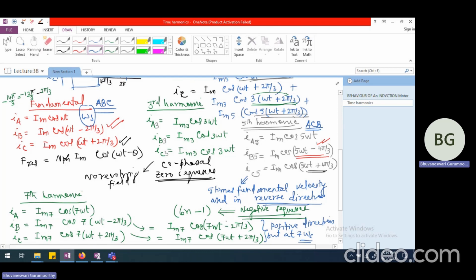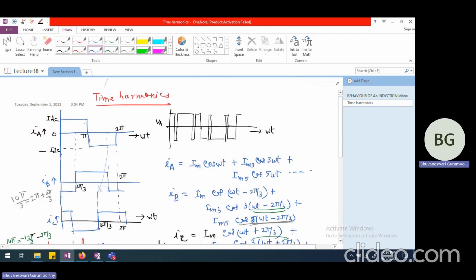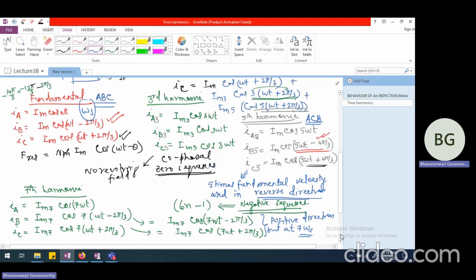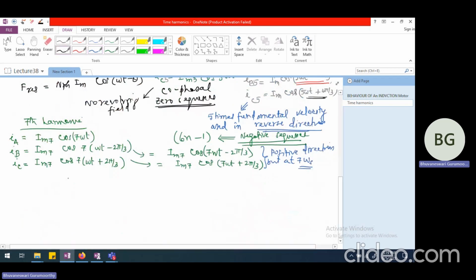If the original synchronous speed is omega s, then this speed is 7 times omega s. So the bottom line is, whenever the stator winding of the induction motor is fed by a current rich in harmonic components, we get multiple revolving fields set up. Let's look at the stator revolving fields that are set up because of harmonic rich current.